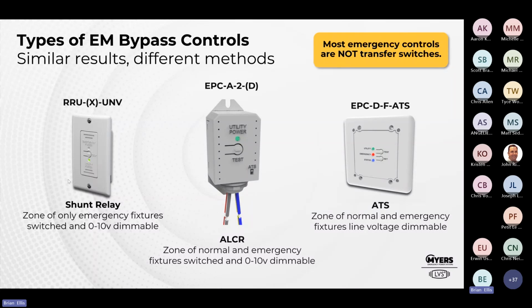The RRU is a shunt relay, with or without the X, which adds the 0 to 10 volt or DALI bypass. Without it, you can use this on 120 or 277. This is the form factor. It can be flush to the ceiling or the wall. You can take the plate off and screw it inside of a junction box. But the main thing with a shunt relay is that every fixture in the lighting control zone must be an emergency light. You can't mix normal and emergency in the same zone.